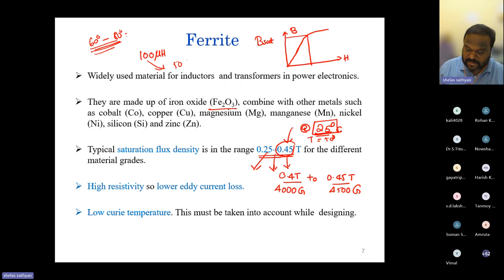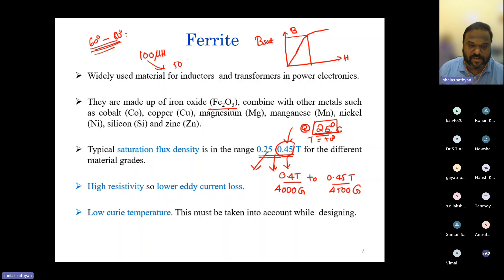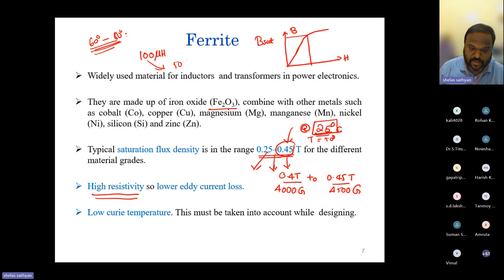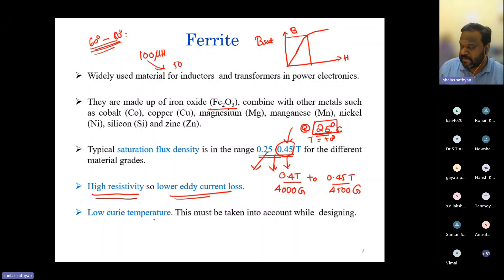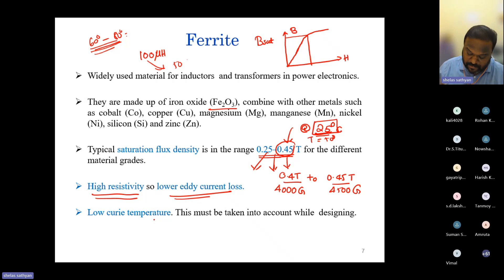Ferrite core is iron oxide with manganese, zinc, or silicon oxides — a mixture that is pre-cast into different shapes. One advantage of ferrite core is its high resistivity, so eddy current losses are very minimum. The hysteresis loss is also very minimum, giving a very small BH curve area, so core losses are very minimum. That is why we can use ferrite for high frequency applications — a typical ferrite core can be used up to megahertz frequency range.